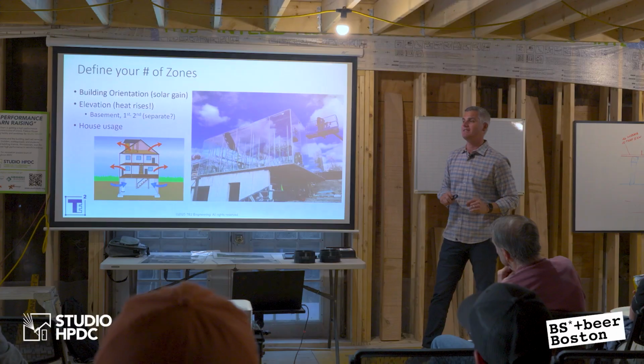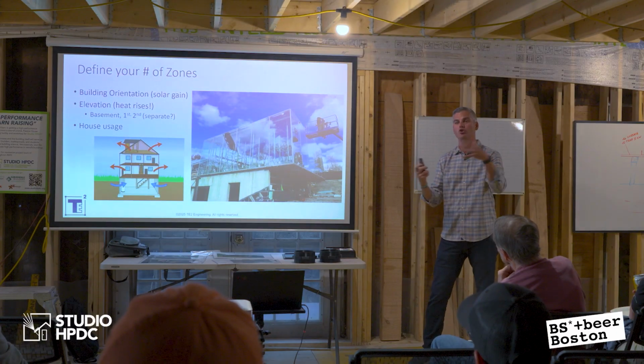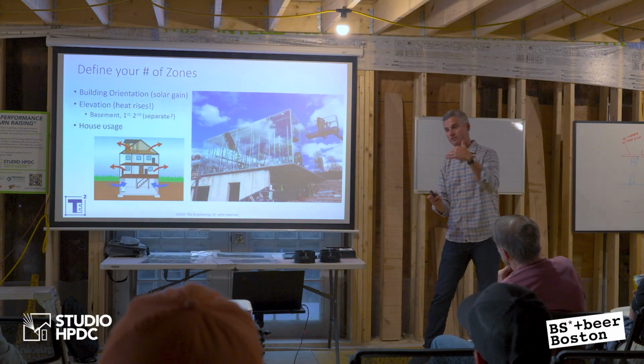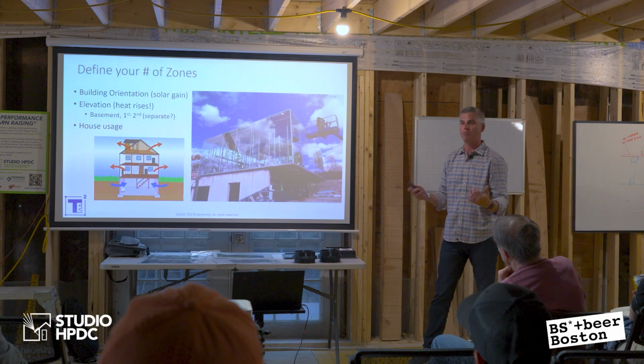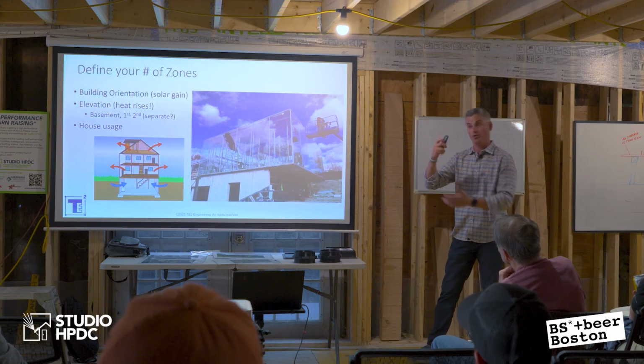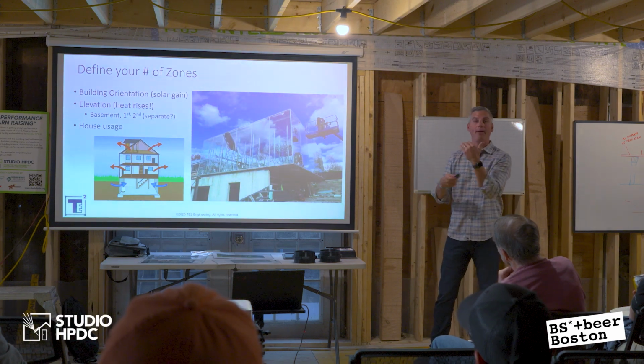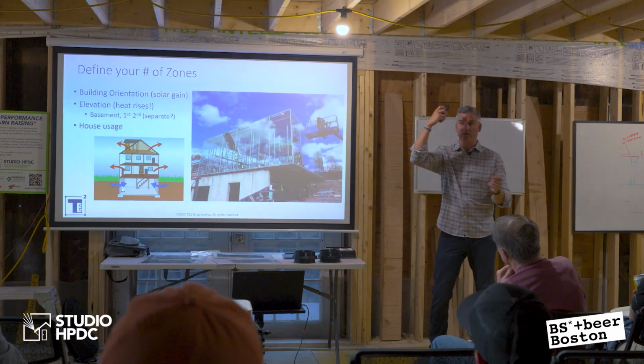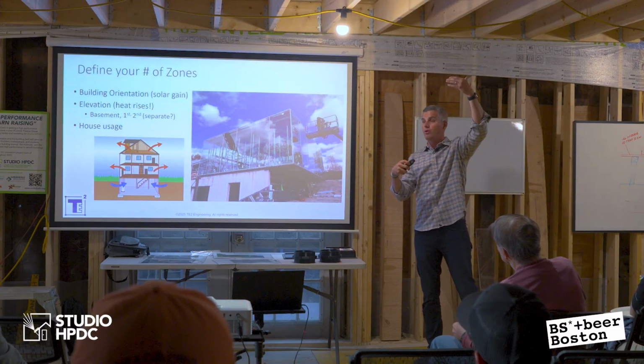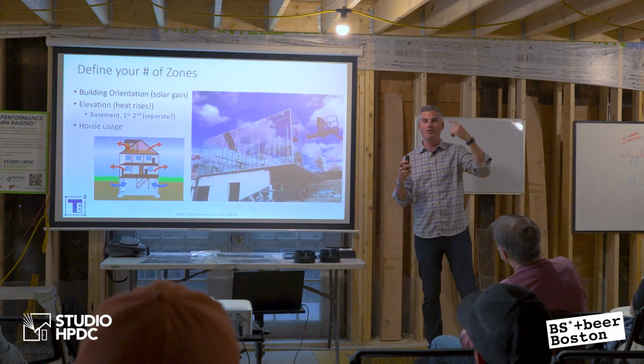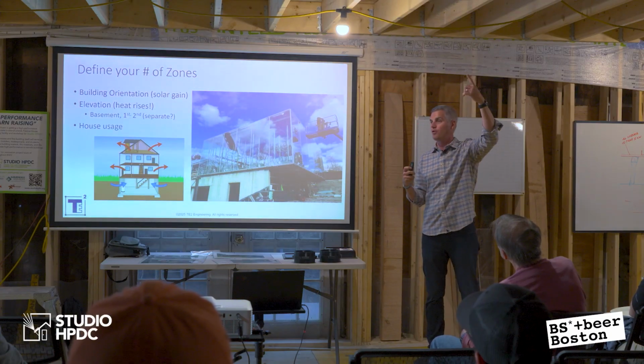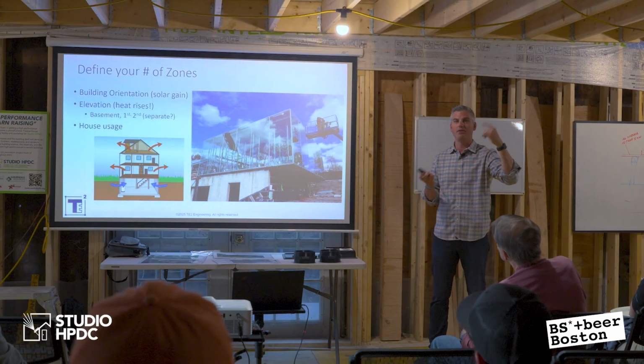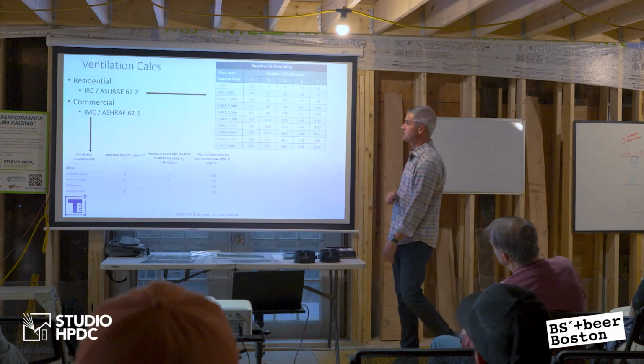Because that's one of the issues that I see, is that they have a zone that covers too much of an area, right? Let's say they did the basement and the first floor on the same thermostat. They put the thermostat upstairs or they put the thermostat downstairs and nobody's happy, right? Or a loft building. They put the one thermostat to cover 2 or 3 floors. And nobody's happy. You're either going to be comfortable on the first floor or you're going to be comfortable on the third floor, and you can't be happy either way, right? So that's always a concern.